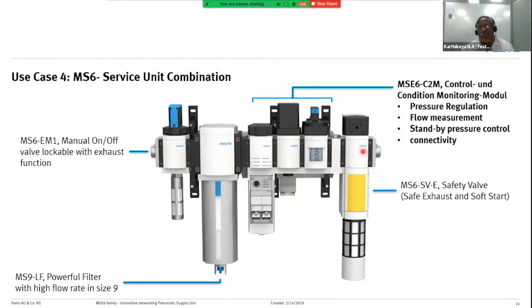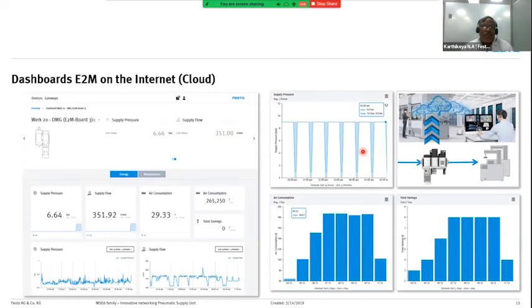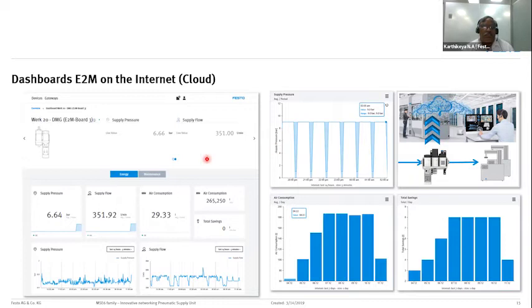You can go up to E level class, safety level. And since the data is being sent to the cloud, you can also make your own dashboards wherein you can see your pressure, flow, consumption, and your total savings. You can also see it on an hourly, daily, monthly, and yearly basis on the cloud. And also you can add analytics so that you know how much the machine has consumed.